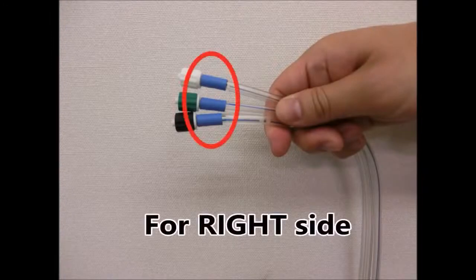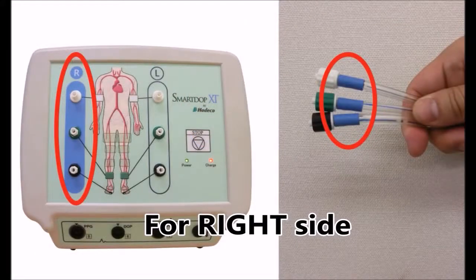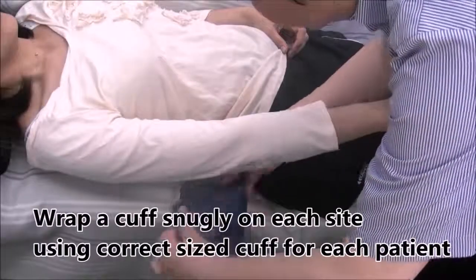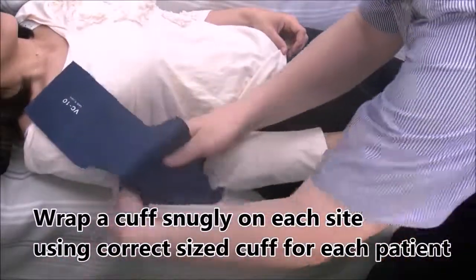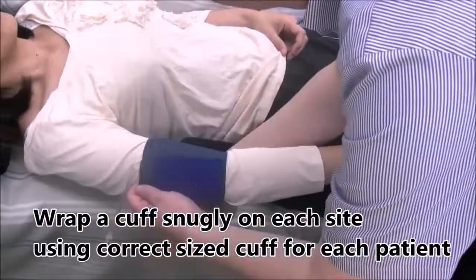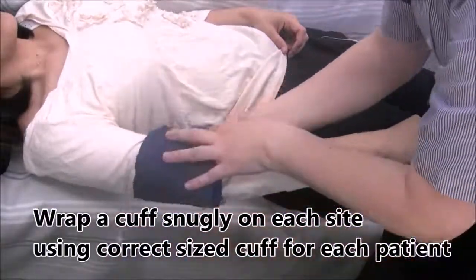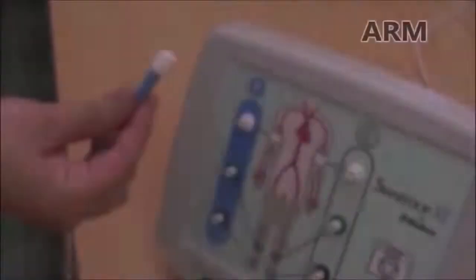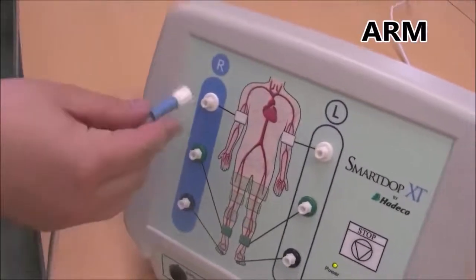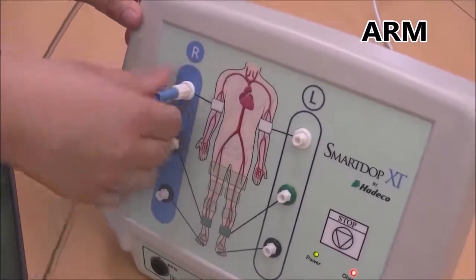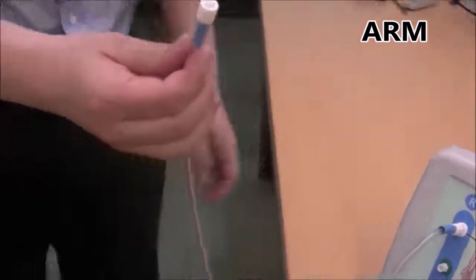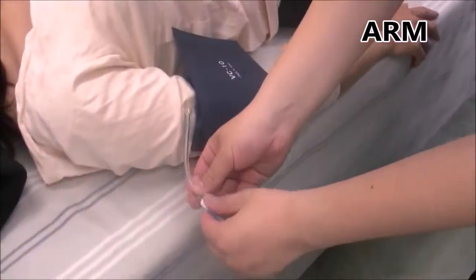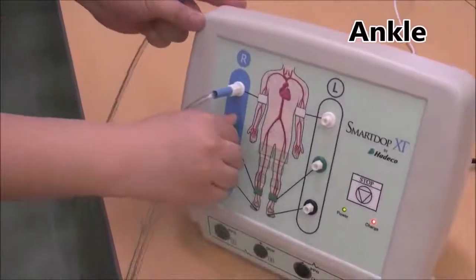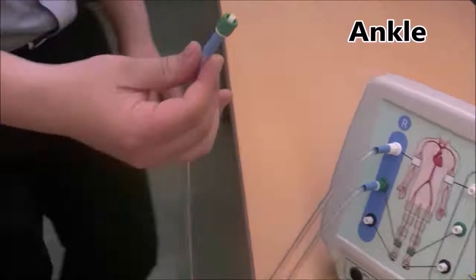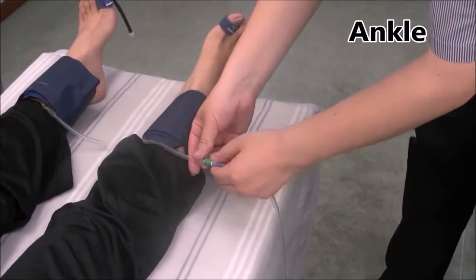All the tubing with the blue colour is for the right side. Wrap a cuff snugly on each site using a correct sized cuff for each patient. The arm cuff is in white, so white tubing should be connected to the white port. The other side should be connected to the right arm cuff. The ankle tubing has a green tip, so connect the green tubing to the green port on the other side to the right ankle cuff.